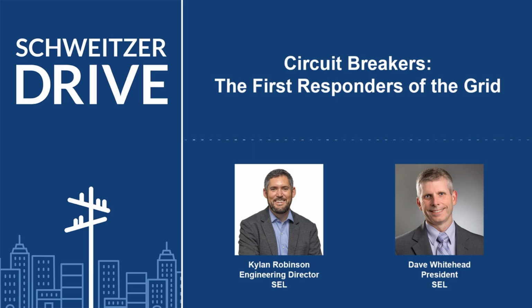Yeah, definitely. So I think current state of the art is probably 2 to 3 cycles to clear a fault on a mechanical breaker, right? And I think it's important to ask, why is speed so important? Our relays are super fast, but who cares? And 2 to 3 cycles is pretty fast, right? But it's important to remember that these are overcurrent situations, short circuit situations, and bad stuff is happening. So you really want to clear that fault as quickly as possible to save equipment, to save lives, to be more efficient, to save energy. So that's why it's important to keep on pushing on speed in this situation.